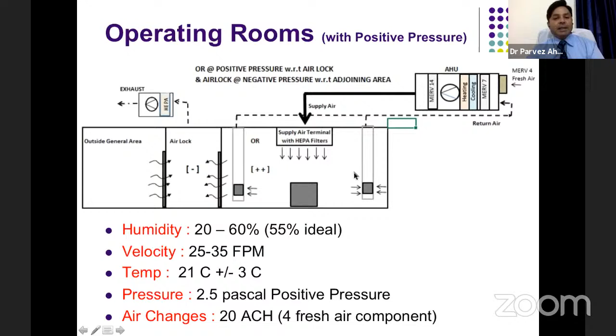This is the last slide of my presentation: operating room with positive pressure. Again, the same model, air handling units, with 2 filters, MERV 7 and MERV 14, installed. Air comes out inside the operation theater through laminar flow where a HEPA filter has been installed, goes into the operation theater with a positive pressure and then comes out. And on the left hand side, there is a clean corridor.